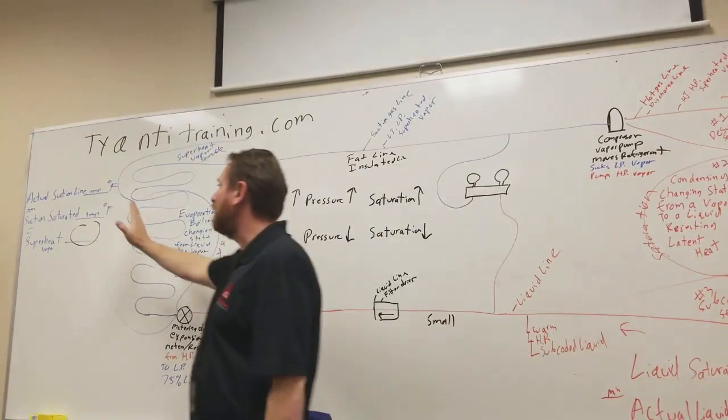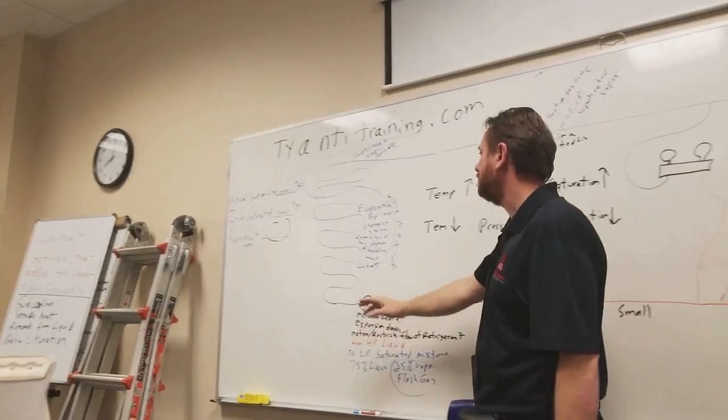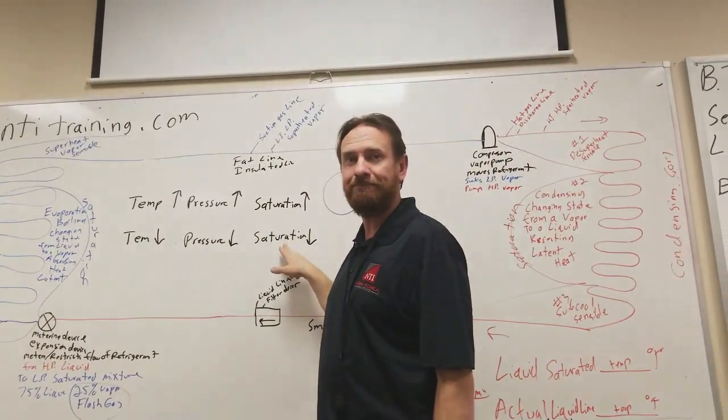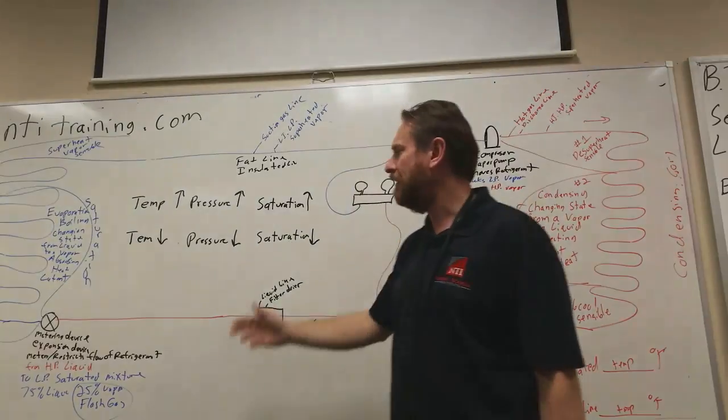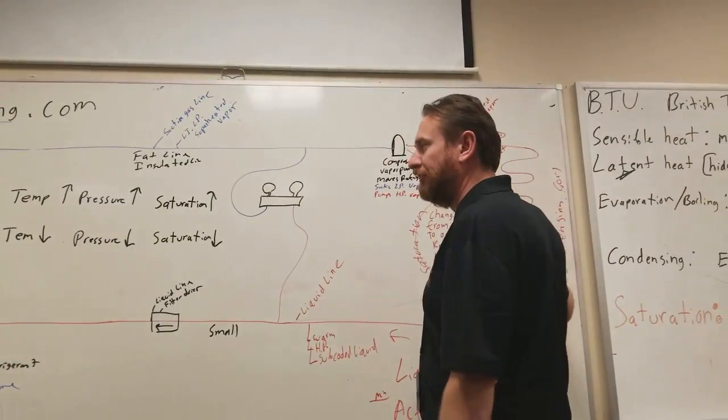So you may have a blocked airflow here. What's a blocked airflow going to cause? Temperature to drop, pressure to drop, saturated temperature to drop, right? So somebody comes through and says, well, it's freezing up, so I'm going to add refrigerant. So they're putting more molecules in over here.